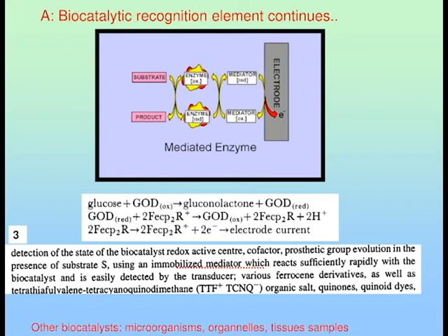Actually, for measurement of the other one, the oxygen, that one will be crucial. Because when you do calibration, you only do one calibration. But if different samples have different original oxygen levels, the drop might not be correct. Alright, so this is one possible way to measure glucose as well. This measurement is independent of oxygen level in the sample.